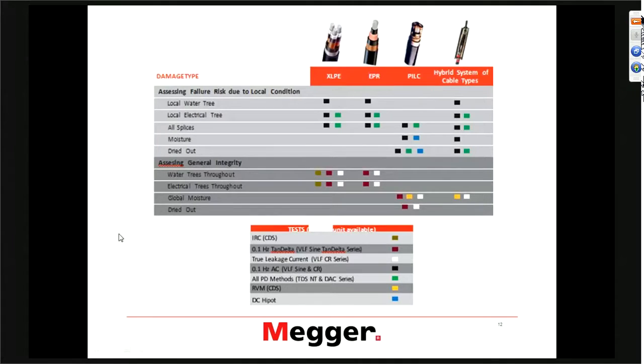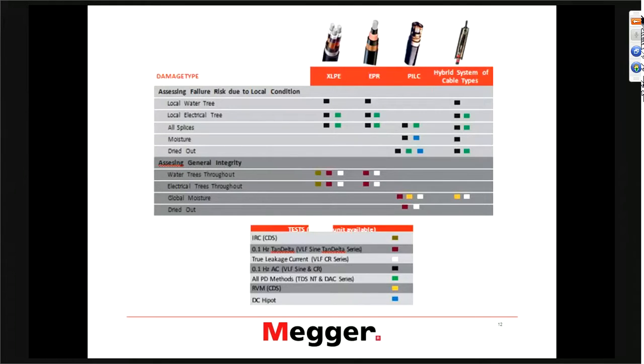Question: Does VLF testing accelerate electrical trees in an XLPE cable if they're already present? Answer: Under VLF conditions, electrical trees at the voltage prescribed in the test will grow faster than under 60 Hz conditions. That is one of the reasons why it's very beneficial to do a VLF test — otherwise, if the growth rate were the same, you could not get the cable to fail during the test time. Electrical trees grow much faster at 0.1 Hz at 2.5 or 3 per unit test voltage. And it's like any type of testing — mechanical or thermal — where you typically test under accelerated conditions. This is the acceleration effect.